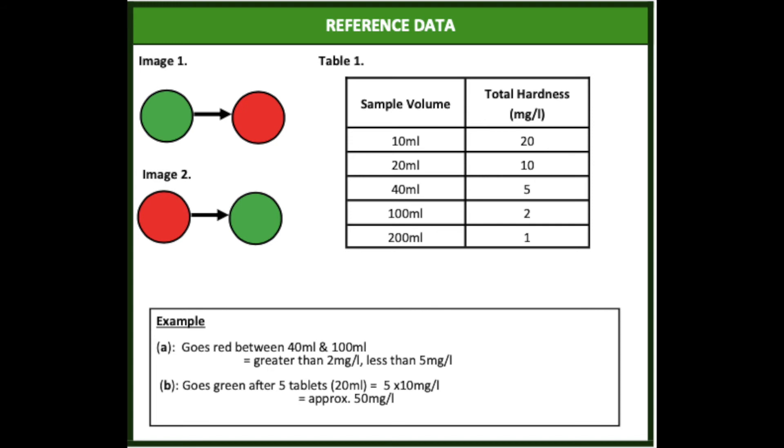If the original 20ml sample goes green from 5 tablets, you'd multiply 5 by 10, giving an approximate total hardness of 50 mg per litre.